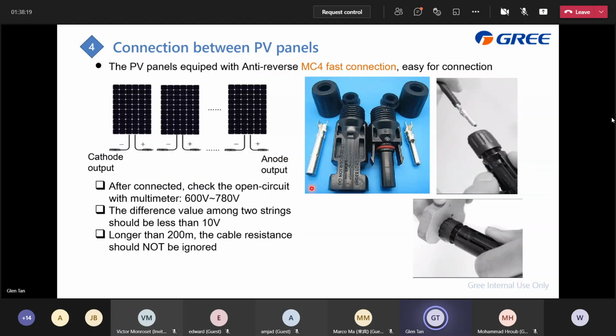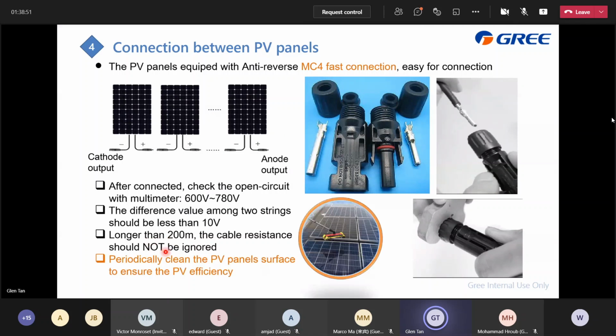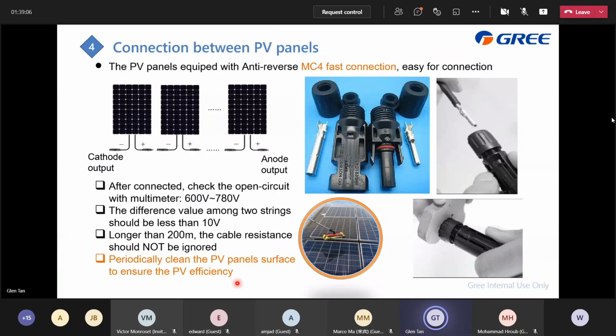For one string, after you connect it, you need to check the open circuit voltage with the multimeter. It should be in this range. And if you have multiple strings, the voltage difference between these 2 strings should be less than 10 volts. Next, if the cable is longer than 20 meters, we need to consider the cable resistance. Last but not least, you need to periodically clean the PV panel surface to ensure the PV efficiency, because if the surface accumulates lots of dust, this will damage the PV efficiency.